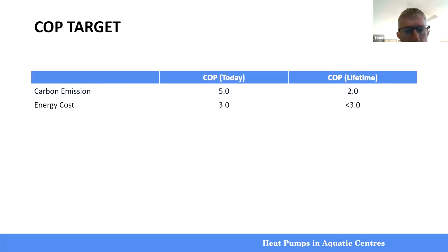So if you wanted to build an aquatic centre today that was able to give you less carbon emission than using a gas boiler, you would need to have a COP of about 5. Now that's possible, but no aquatic centre built today would have had that COP yet. But luckily the government has some future reductions in its, or improvements in its power supply, and the overall efficiency you'll need over the lifetime of a heat pump, if you put one in today, would only need to be a COP of 2 to be better than a gas boiler in a heating situation. And a COP of 2 is quite easily achieved. Most heat pump systems would do better than that over their life.